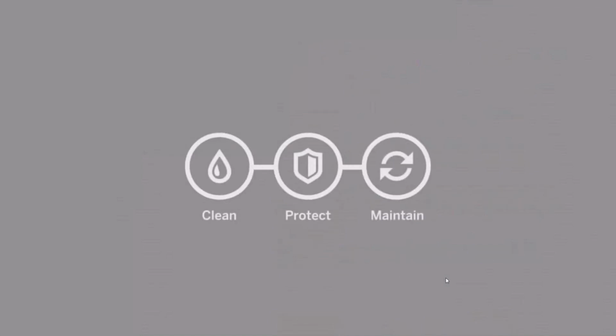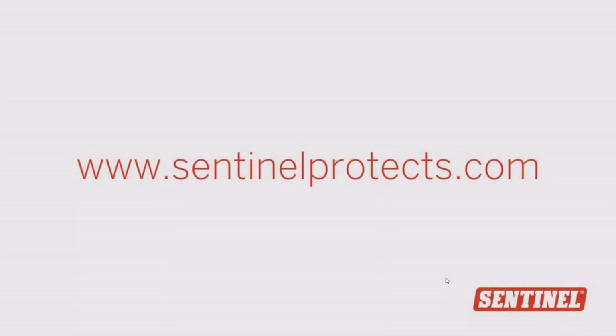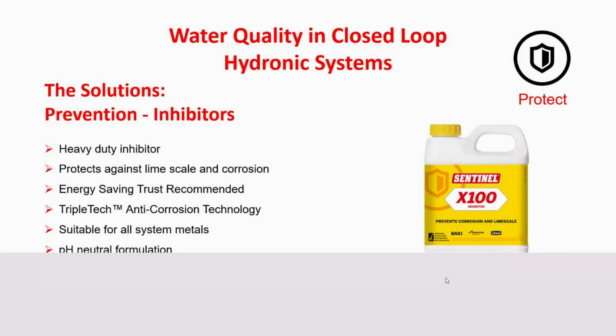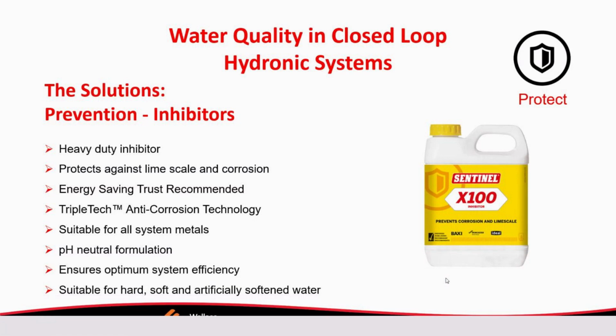And that's the key thing. The next thing you need is an inhibitor. In this case, this is a rapid dose cleaner, but the inhibitor is this product called X100. What this inhibitor does is it works very well to make sure that the corrosion stabilizes in there, prevents rust, prevents magnetite. It does a lot of things to keep corrosion and pitting, prevents scale buildup. It does all those things.